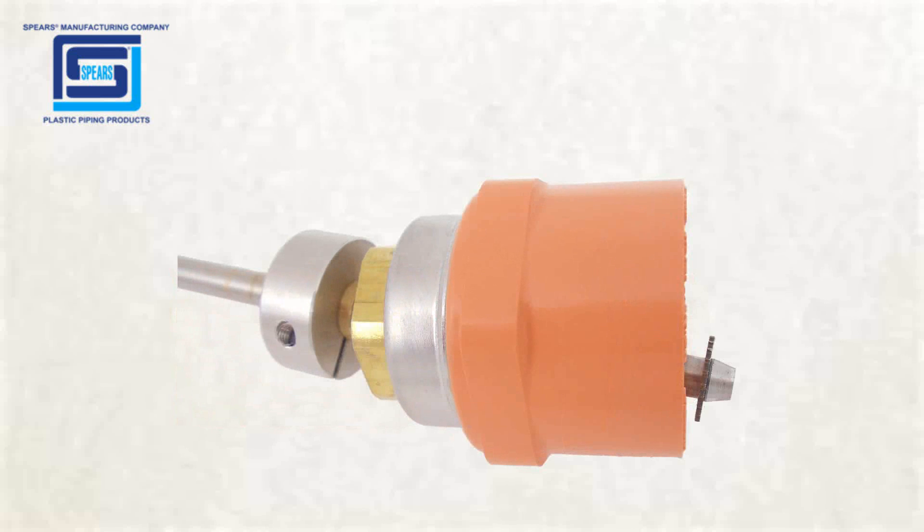You will now need to adjust the depth for the inside pipe cutter. You are going to want your cut right above the bead of the solvent cement. In this example we inserted the inside pipe cutter into a new Torque Safe Sprinkler Head Adapter to determine our length right above where the bead line would be.